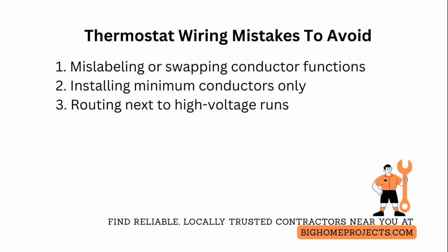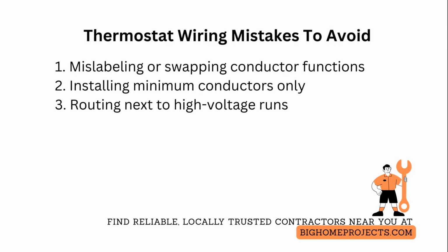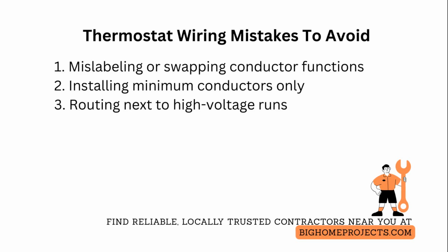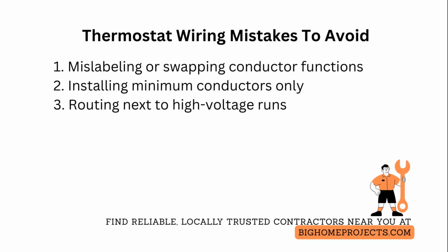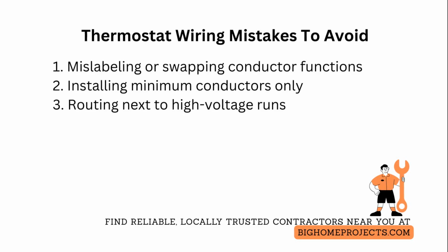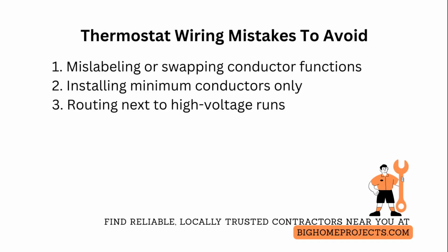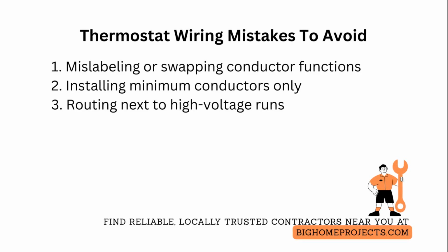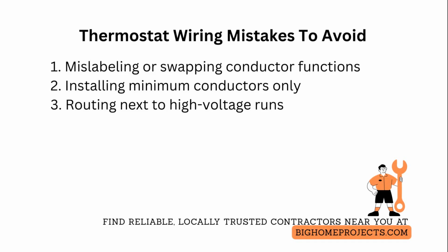One of the most common thermostat wiring mistakes is mislabeling or swapping conductor functions, which breaks smart thermostat power and can blow fuses. Fix this by labeling both ends, testing continuity, and mapping colors to functions before hooking up. One of the biggest installation issues is running only the minimum number of conductors, which forces future rewiring for upgrades like integrated humidifiers or zoning.